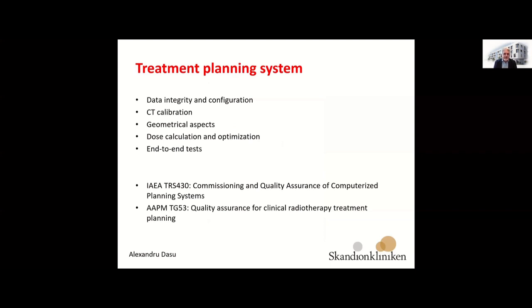Treatment planning system, it's a central critical system in radiation therapy. So for a treatment planning system, you have to perform a regular check, at least at every upgrade of the system, but also an upgrade of the IT system, where you have to check the data integrity and the configuration files, all the models that you are having, all the settings for your system, they have been preserved. You have to look at the CT calibration. The calibration curves are still there after the intervention. You have to look at the geometrical aspects.